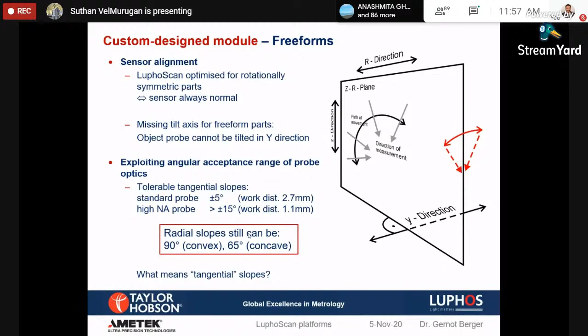So this all depends on the application, depends on the requirement. So we have different solutions to fulfill their needs. This is one example of free-form measurement. The tangent slope is less than plus minus 5 degrees. We call it a mild free-form or lesser free-form effect. So the standard LuphoScan machine and standard probe can measure it.